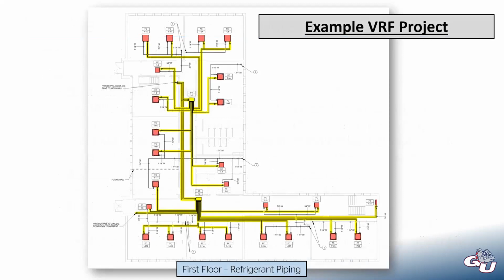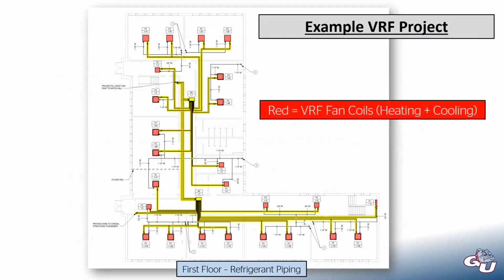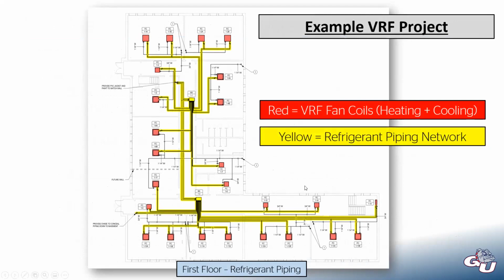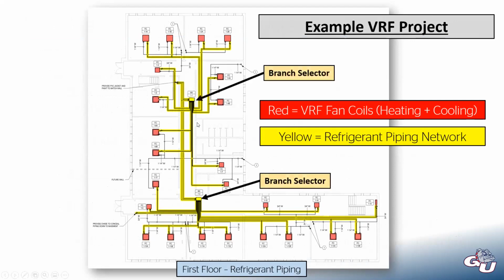And so if you think back to when I talked about this building, this is Tico Elementary. I had a little mini lecture on it where I talked about it as kind of a project highlight for what a retrofit project might look like. But now you can look at this with a little bit different lens now that you know what's going on here. So the red boxes, those are the VRF fan coils. Those are in the ceiling, providing the heating and cooling. The yellow is our refrigerant piping network. We have our two branch selectors there, so you can see the three pipes coming into the branch box, and then you've got that spaghetti of refrigerant pipe going all over the place to hit all of these fan coils. Same thing down here, hit all of these fan coils on this side of the building.